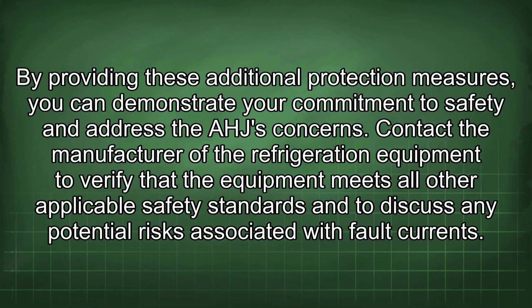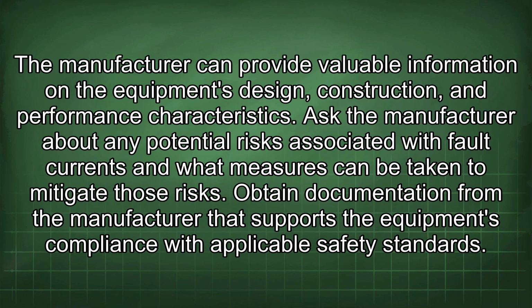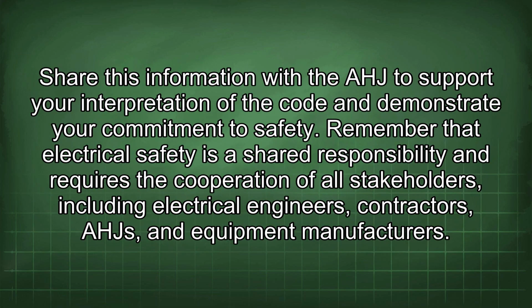Contact the manufacturer of the refrigeration equipment to verify that the equipment meets all other applicable safety standards and to discuss any potential risks associated with fault currents. The manufacturer can provide valuable information on the equipment's design, construction, and performance characteristics. Ask the manufacturer about any potential risks associated with fault currents and what measures can be taken to mitigate those risks. Obtain documentation from the manufacturer that supports the equipment's compliance with applicable safety standards. Share this information with the AHJ to support your interpretation of the code and demonstrate your commitment to safety.